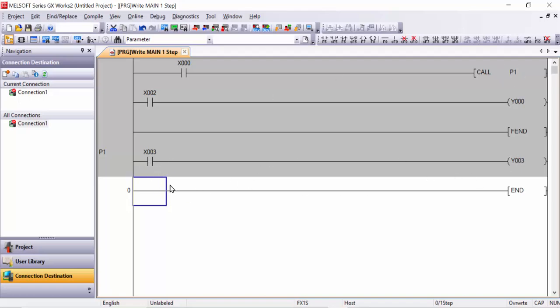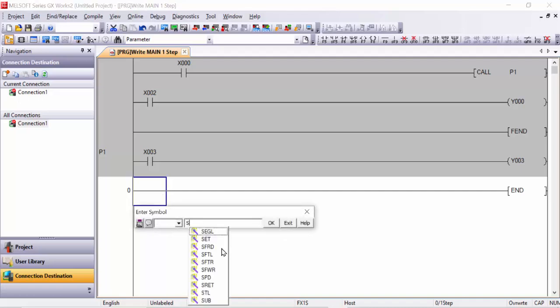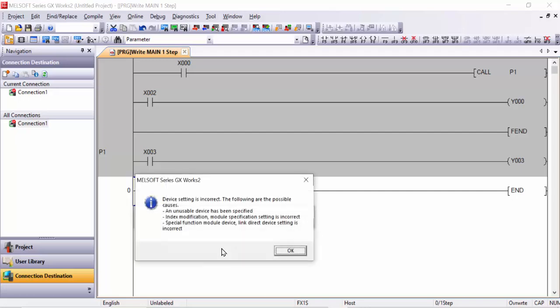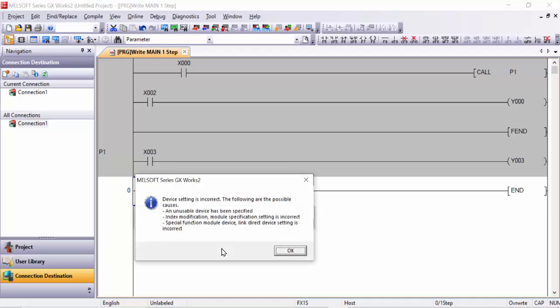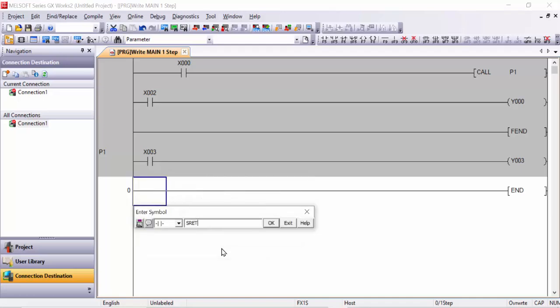After the subroutine program, we must write the return instruction. Double click here and write S-R-E-T — that means subroutine return. This SRET instruction sends the program back after the P1 subroutine has finished executing and returns control to the main program.